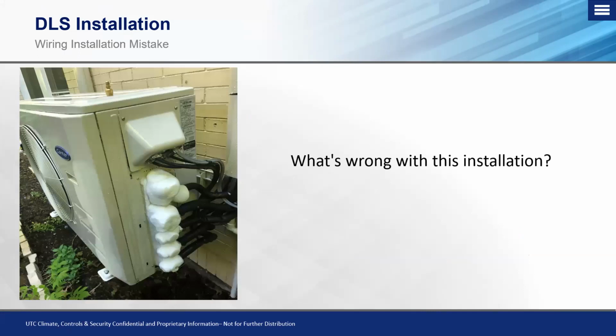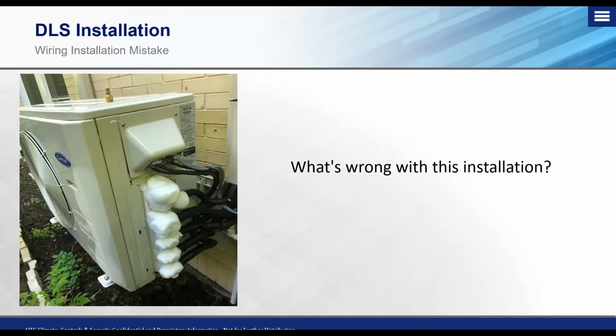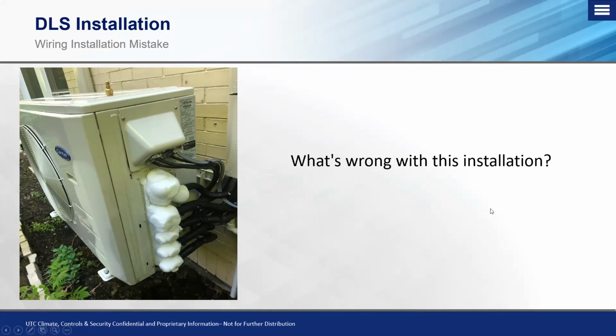Okay, now this is my favorite one. I always call this the snow cone syndrome, and this typically happens in the summertime with a brand new installation. So you get a service call, you're out on the service call, and you go up to the outdoor unit, and this is what you see. Okay, you see your snow cone syndrome.